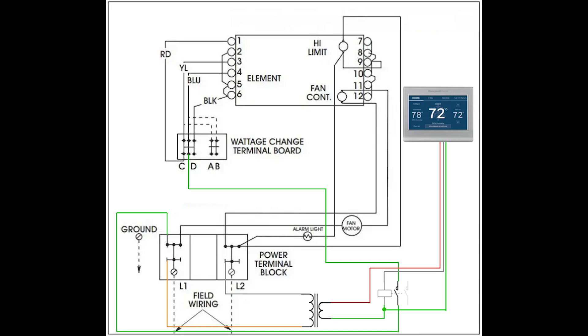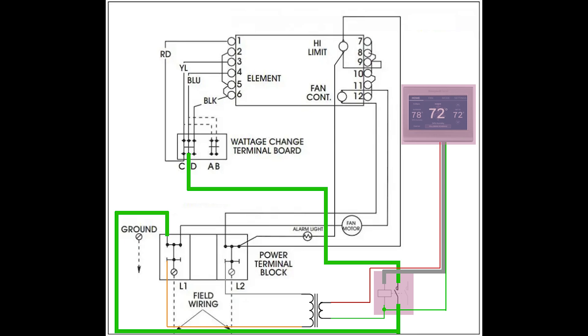Okay, that was a lot. But simply, when the thermostat calls for heat, it will energize the W terminal, sending 24 volts to the contactor coil, which will close the contactor and allow current to flow to the heating element.